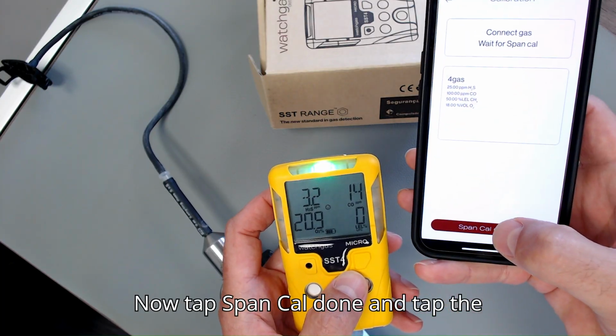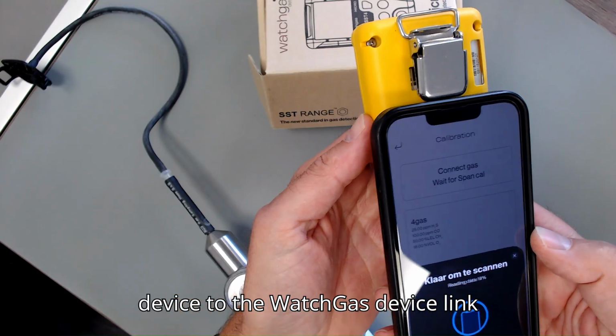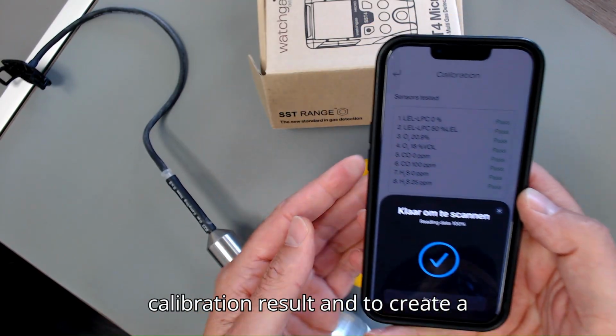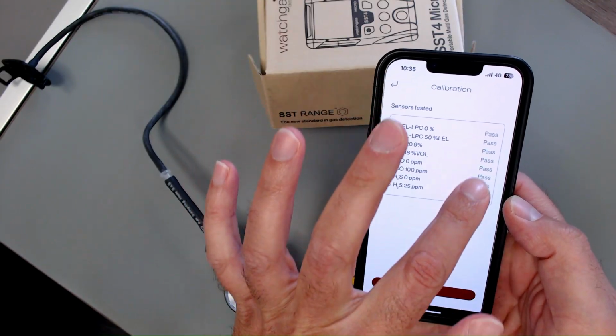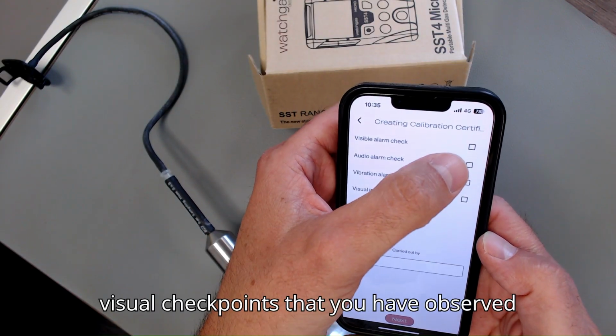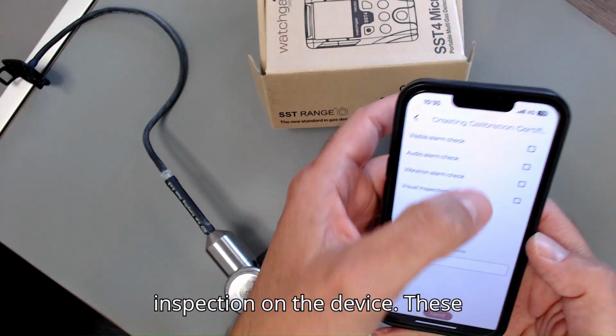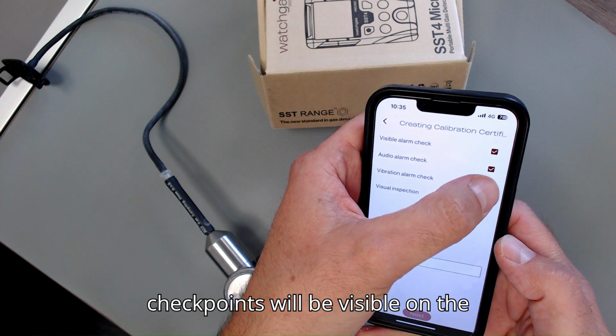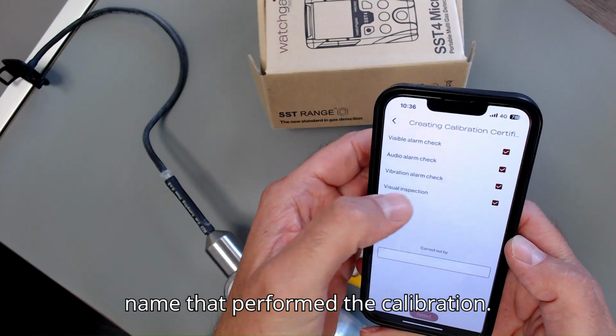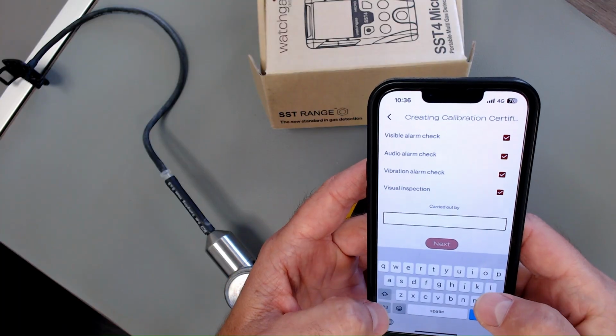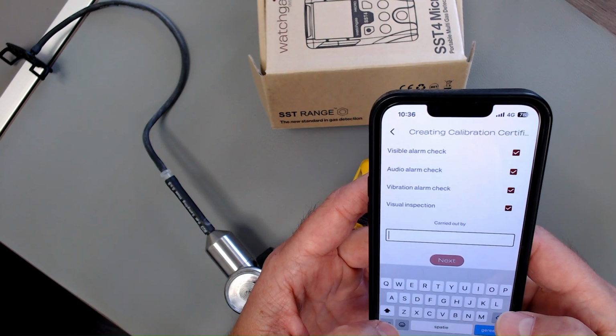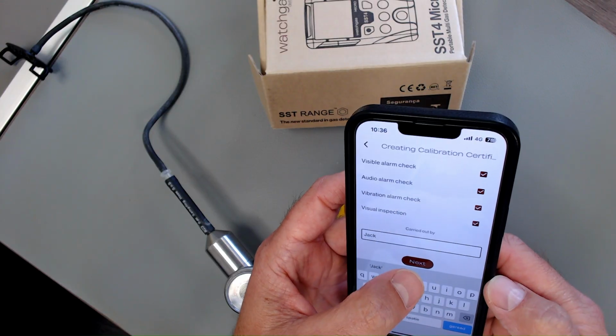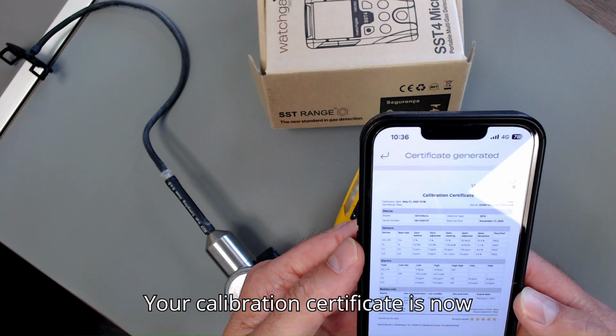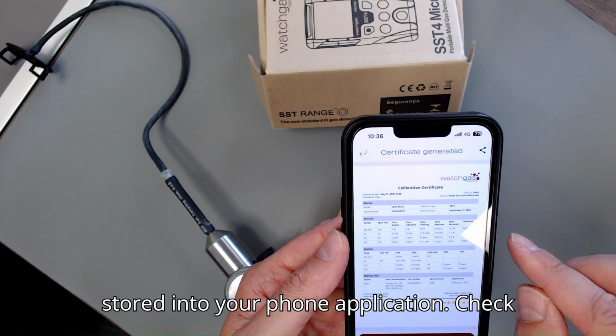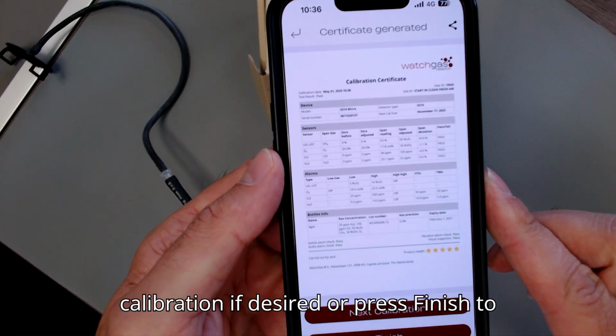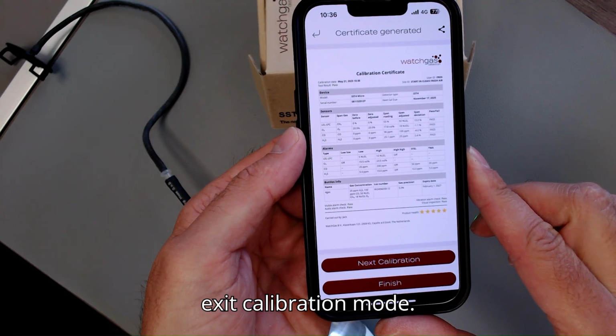Now tap Span Cal Done and tap the device to the WatchGas device link application to obtain the pass calibration result and to create a calibration certificate into the app. Checkmark the indicated acoustic and visual checkpoints that you have observed yourself together with the visual inspection on the device. These checkpoints will be visible on the certificate together with the entered name that performed the calibration. Your calibration certificate is now stored into your phone application. Check this for correctness and start a new calibration if desired, or press Finish to exit calibration mode.